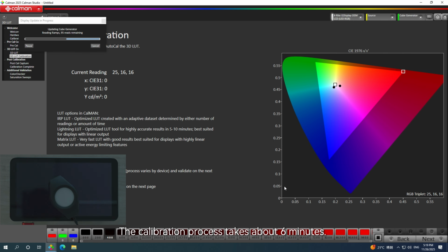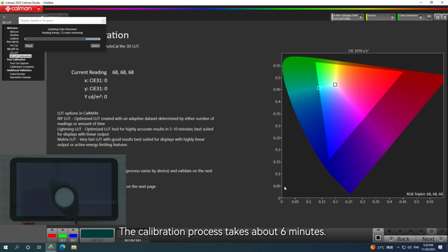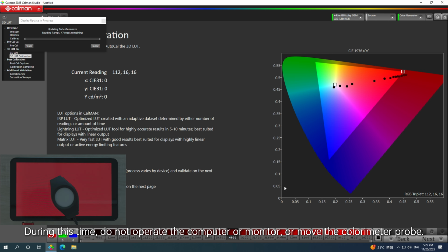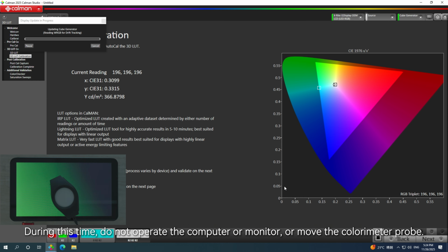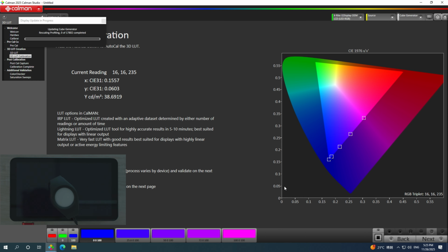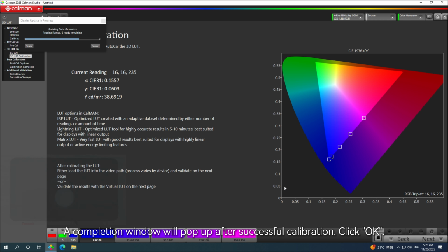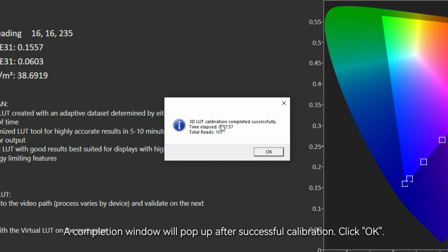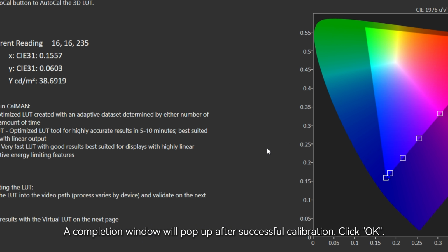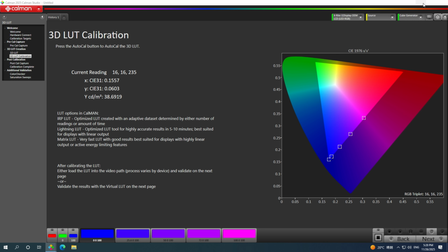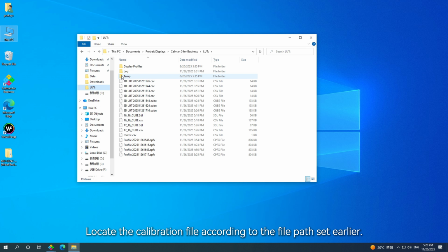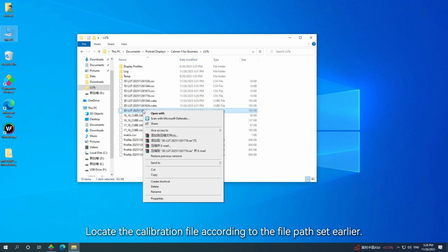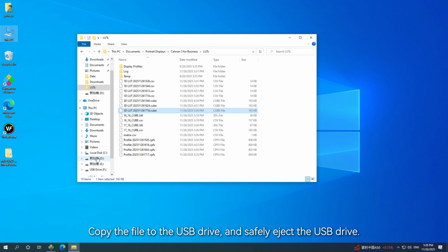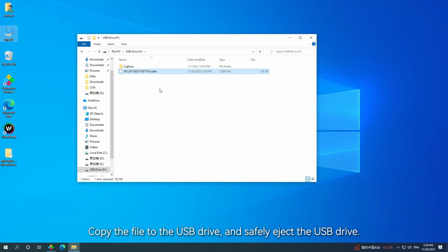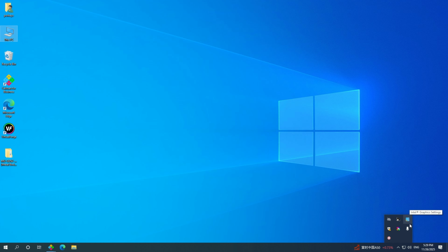The calibration process takes about 6 minutes. During this time, do not operate the computer or monitor, or move the colorimeter probe. A completion window will pop up after successful calibration. Click OK. Locate the calibration file according to the file path set earlier. Copy the file to the USB drive and safely eject the USB drive.